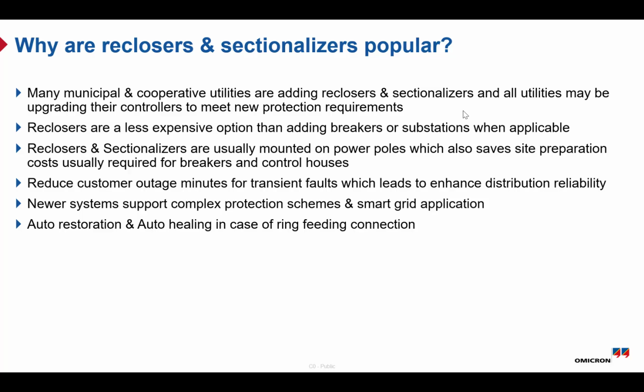Also, by dividing the network into smaller sections, fewer customers are affected when a permanent fault happens. Another key advantage is the cost. Reclosers are much more economical compared to installing a full substation or additional circuit breakers. They are usually mounted on existing power poles, which means lower installation and site preparation costs. In addition, modern systems support more advanced protection schemes and smart grid applications. And in a network with ring configuration, they enable features like automatic restoration and self-healing. So overall, they improve reliability, reduce costs, and support more advanced grid operation.